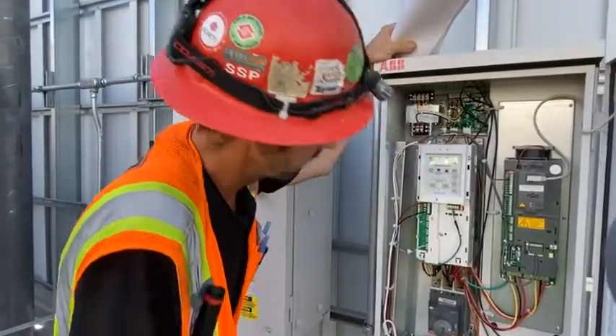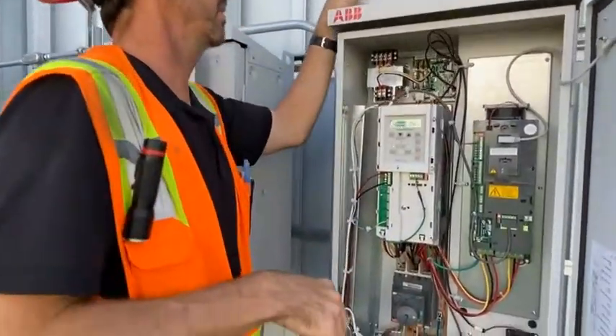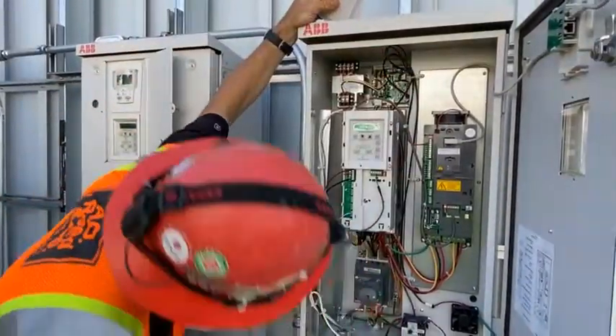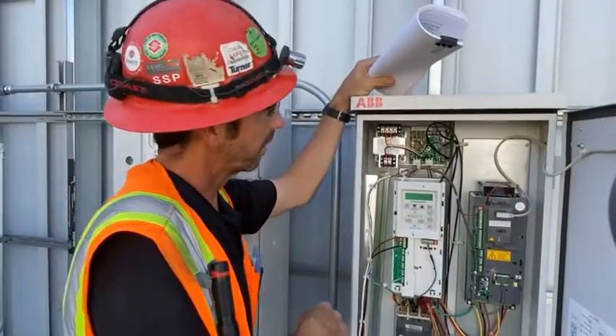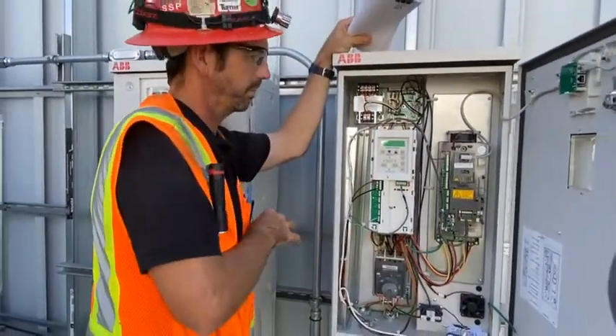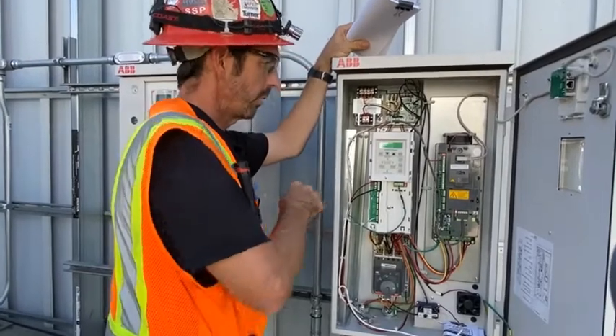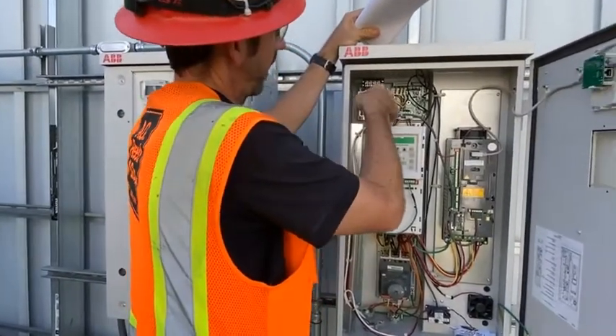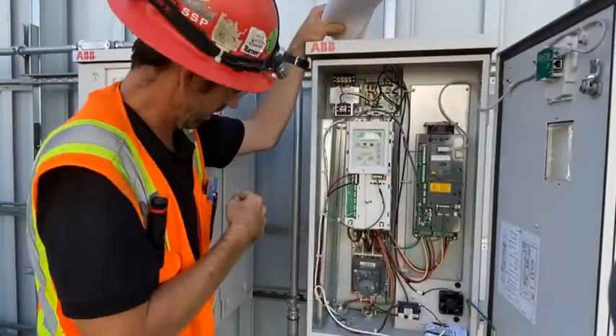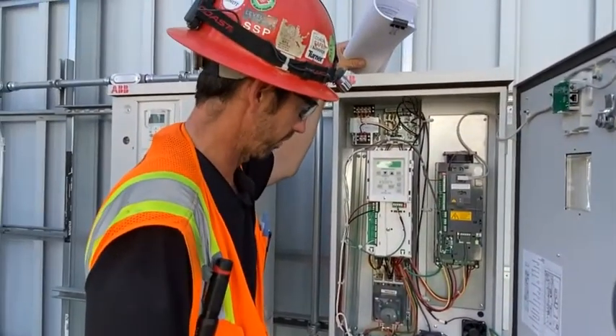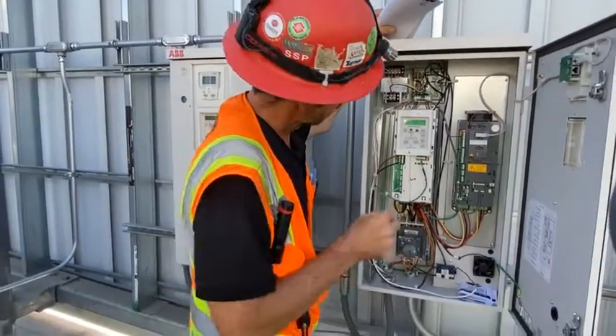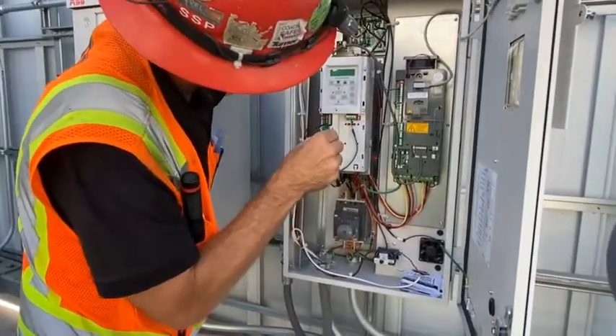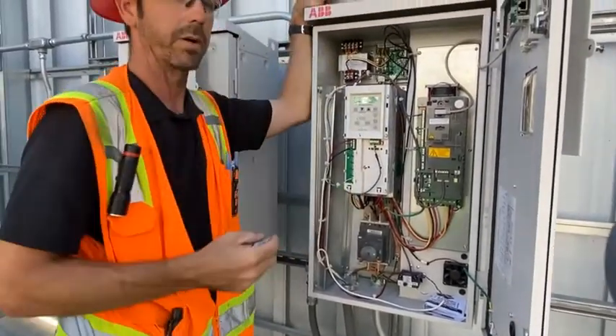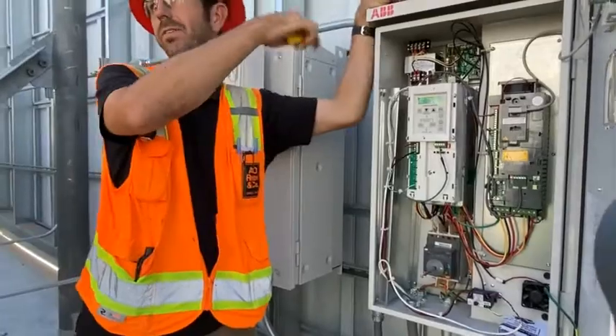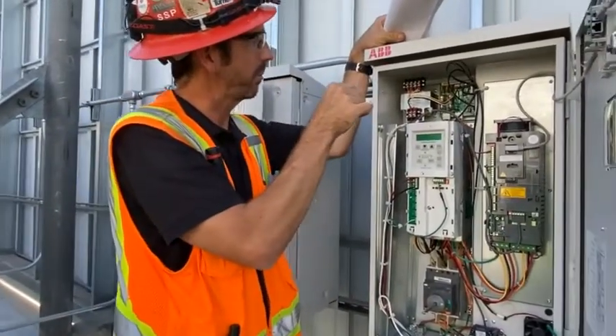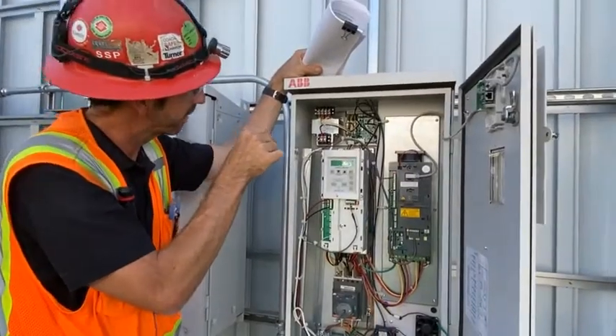There are fans in here. We have a couple of cooling fans, so those need to be checked. I don't believe there are any filters on this unit. We do have a heater assembly up here though. There's a heater strip right over here that's going to help maintain temperature in the drive compartment, so in the wintertime when it gets super cold out here, we don't have condensation all over the outside of the unit. And this is the heater assembly controller right up here.